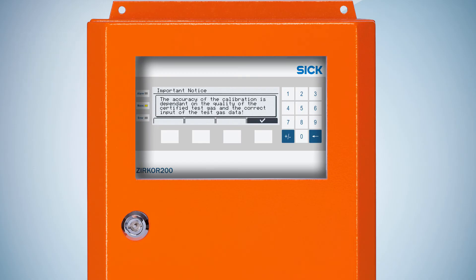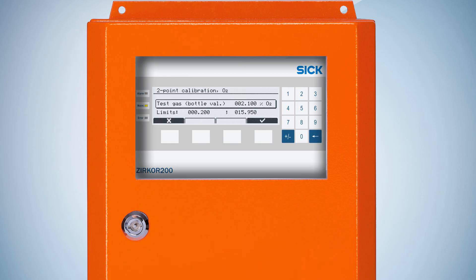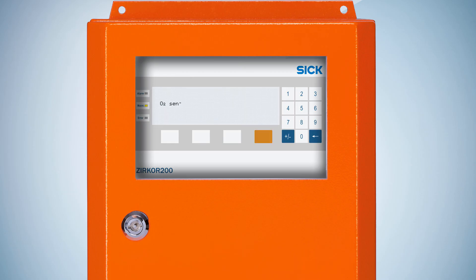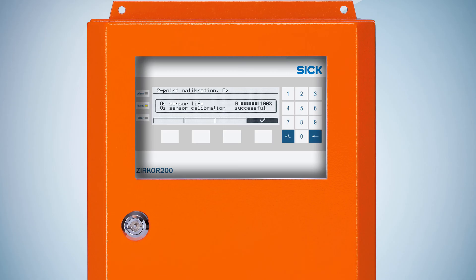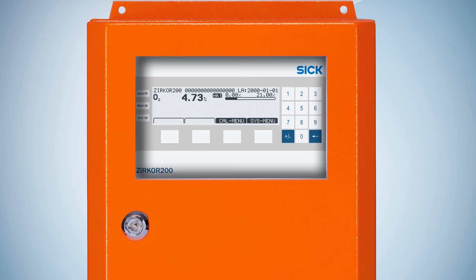The accuracy of the calibration is dependent on the quality of the certified test gas and the correct input of the test gas data. Due to that, please insert the value on your test gas bottle and make sure that the value is correct. After all these steps, the ZIRKOR200 is calibrated successfully. Thank you for watching this tutorial.